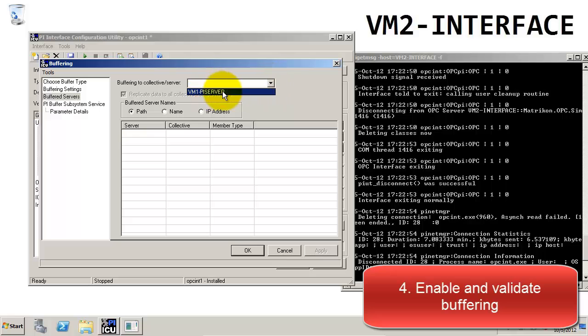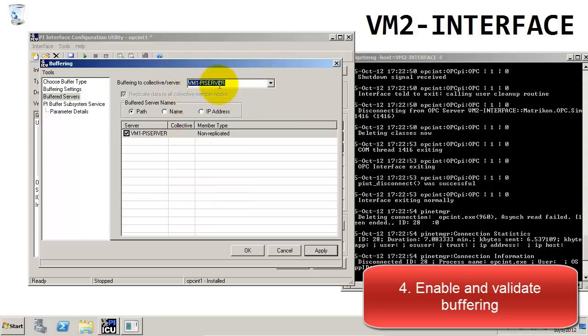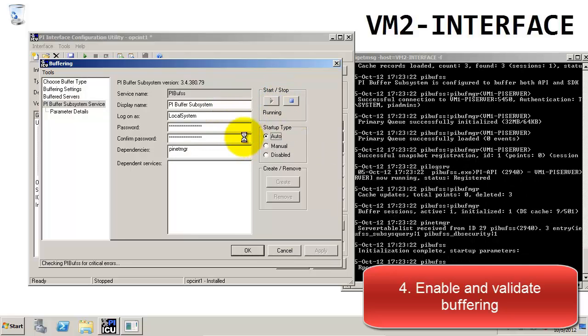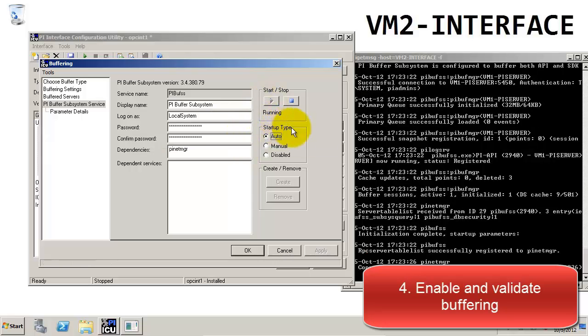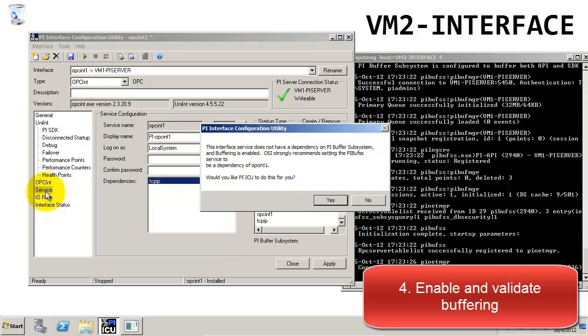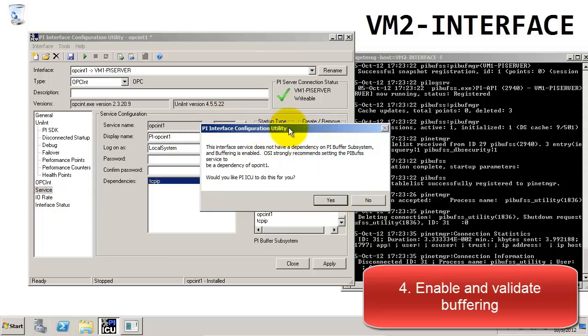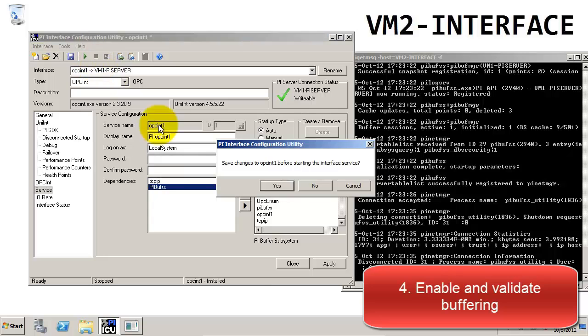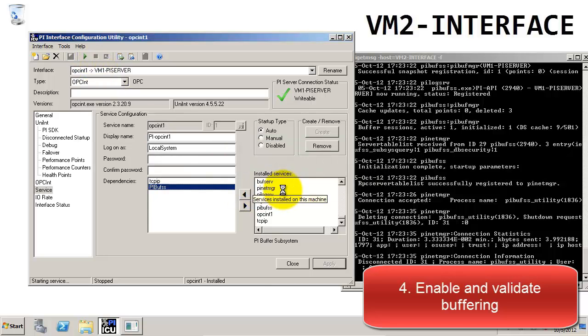In the Buffered servers, we'll choose our PI Server as the server to buffer the data to. We want to make sure that under the Buffered Server names, we choose Name as the option, since our host is specified by its name and not by the IP address or the path. We'll go ahead and start the Buffer subsystem. Once we've started the PI Buffer subsystem, we'll go back to the ICU page. When we click on the Service tab of the interface, ICU will prompt us to add the dependency for PI Buff SS, and we'll click Yes. When we restart the interface, all of the data will now pass through the buffer before going to the PI Server.